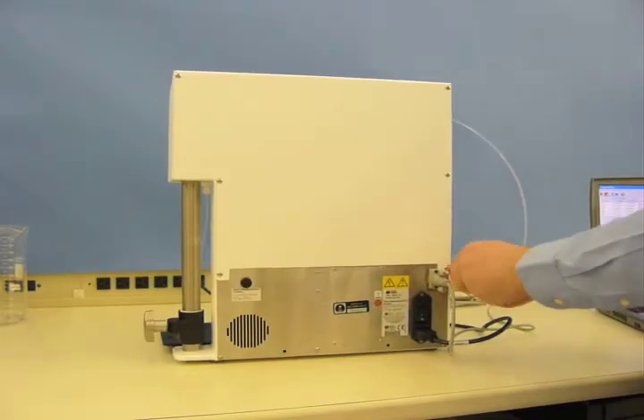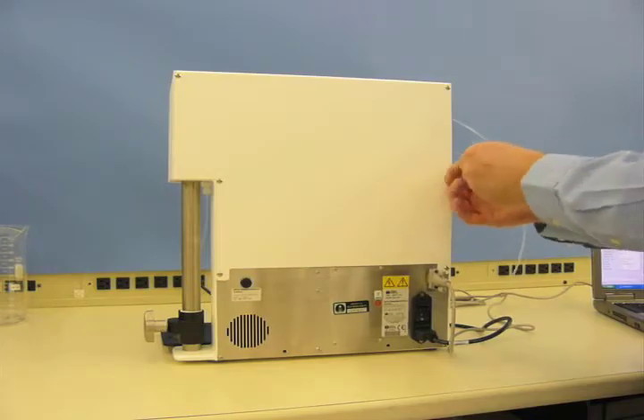Rotate the sampler so that you have access to the rear panel screws and use a 3/32 inch allen head wrench to remove each of the six button head screws securing the rear panel.